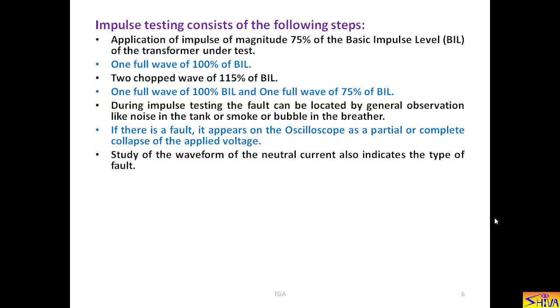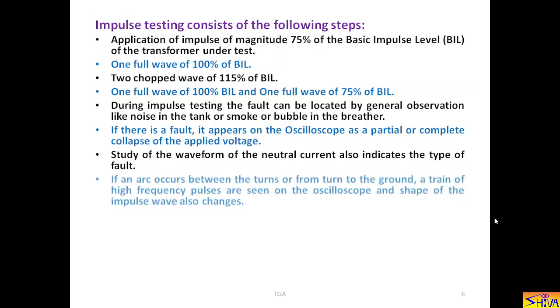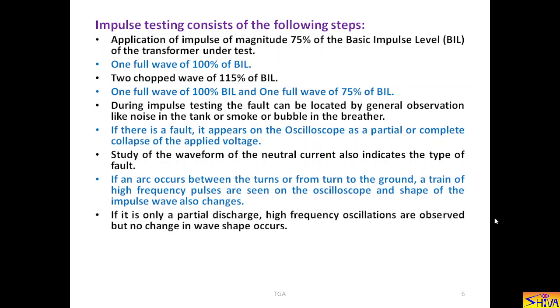Study of the waveform of the neutral current also indicates the type of the fault. If an arc occurs between the turns or from turn to the ground, a train of high-frequency pulses are seen on the oscilloscope, and shape of the impulse wave also changes. So, these all are the indications of the faults and their nature. If it is only a partial discharge, high-frequency oscillations are observed, but no change in wave shape occurs.